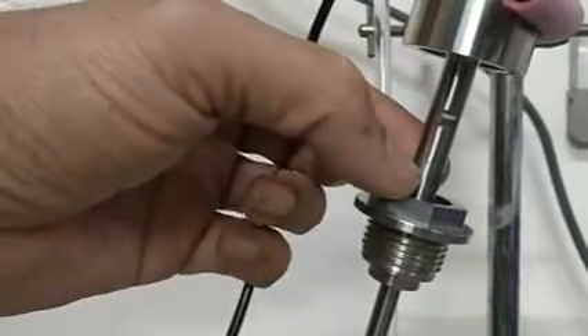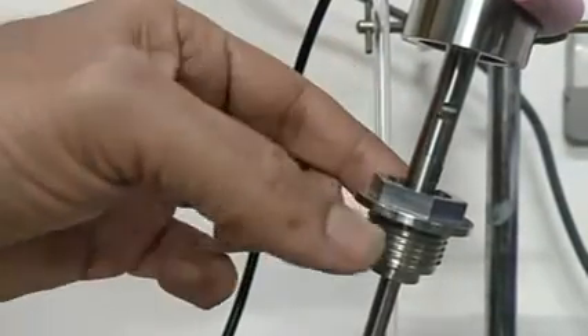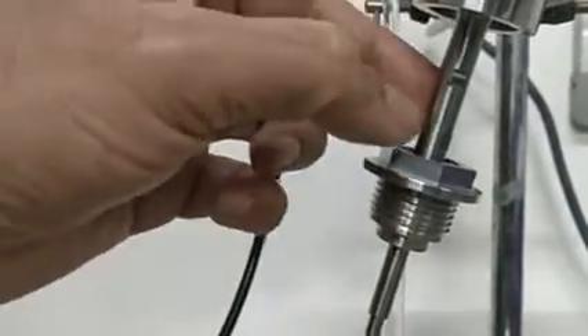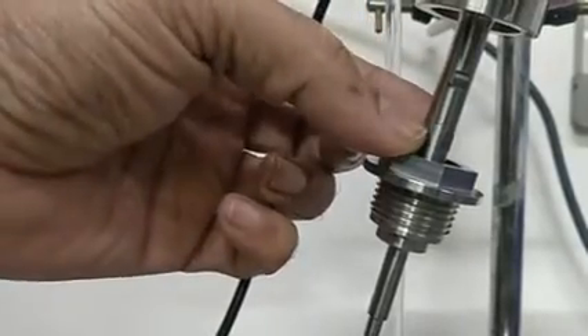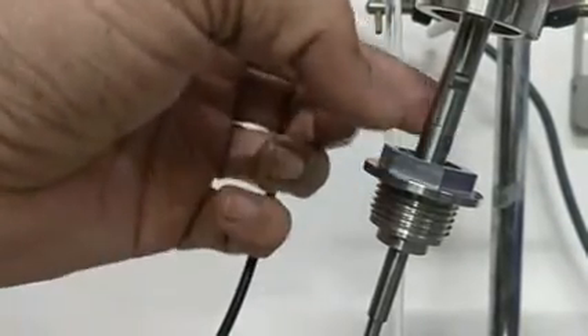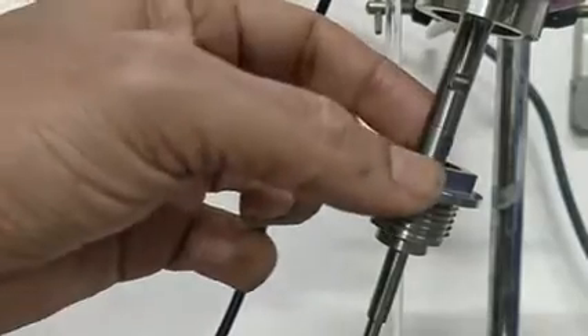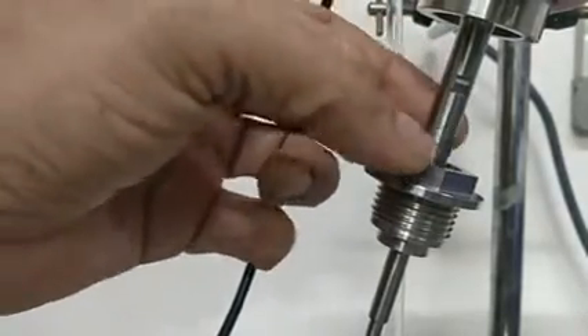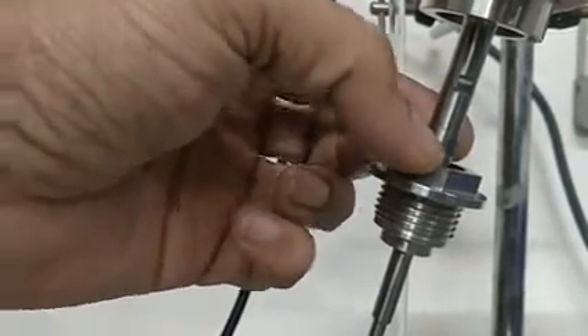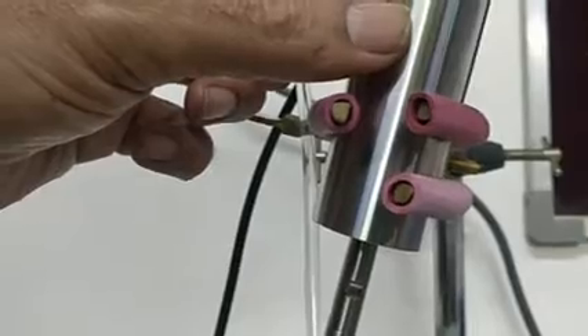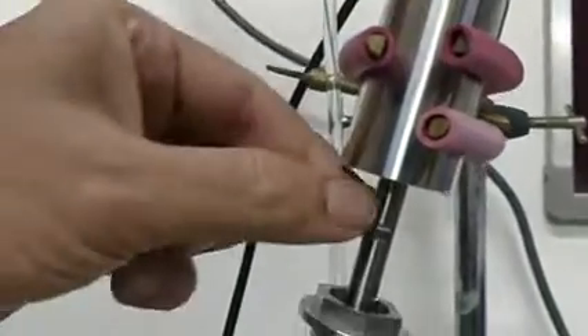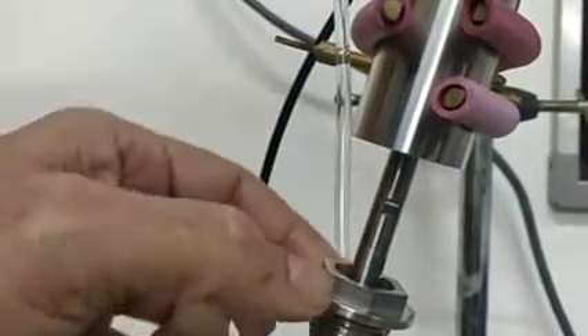This extension tip is made up of titanium, and you can see it is tightened on threads. If you have to remove that, use both spanners, because if you use only one spanner, there are some wires inside this nozzle that may break and your warranty will void. So always use two spanners when you have to open this.